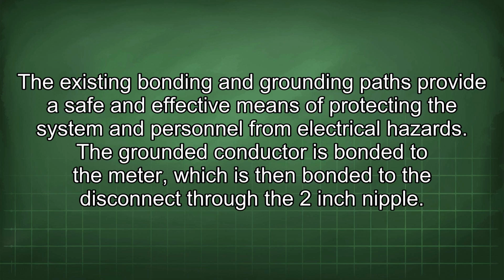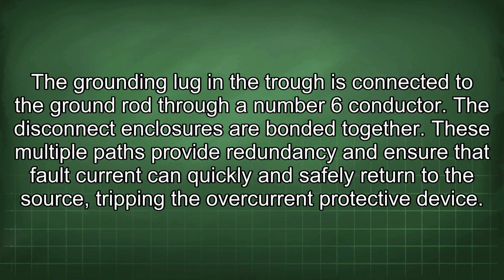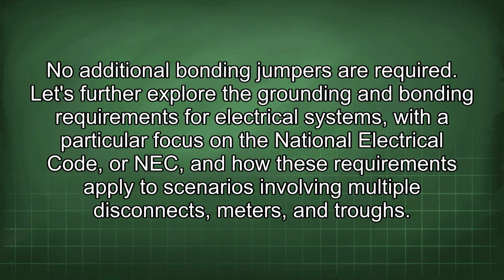The grounded conductor is bonded to the meter, which is then bonded to the disconnect through the 2-inch nipple. The grounding lug in the trough is connected to the ground rod through a number 6 conductor. The disconnect enclosures are bonded together. These multiple paths provide redundancy and ensure that fault current can quickly and safely return to the source, tripping the overcurrent protective device. No additional bonding jumpers are required.